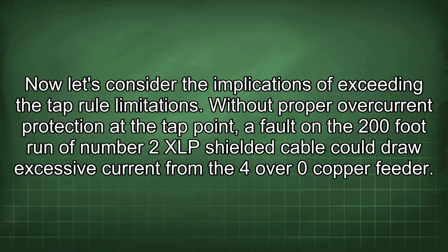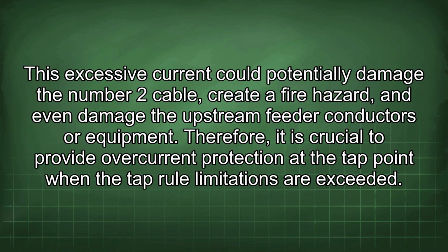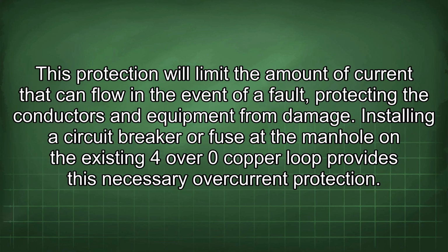Without proper overcurrent protection at the tap point, a fault on the 200-foot run of number 2 XLP shielded cable could draw excessive current from the 4/0 copper feeder. This excessive current could potentially damage the number 2 cable, create a fire hazard, and even damage the upstream feeder conductors or equipment. Therefore, it is crucial to provide overcurrent protection at the tap point when the tap rule limitations are exceeded. This protection will limit the amount of current that can flow in the event of a fault, protecting the conductors and equipment from damage.